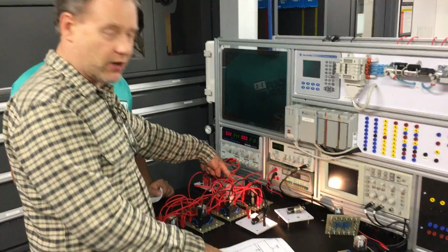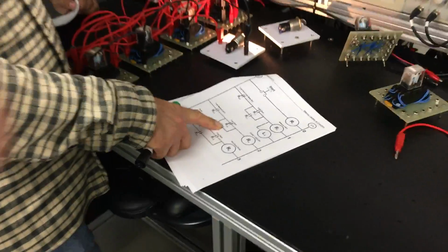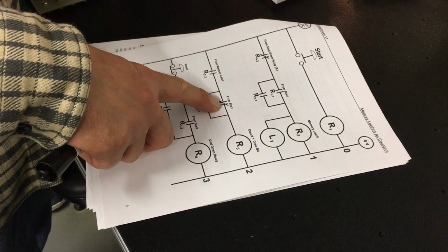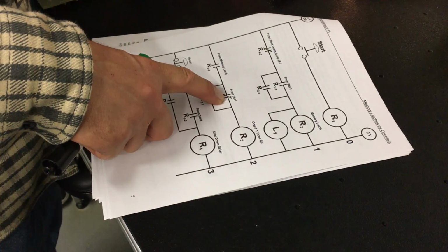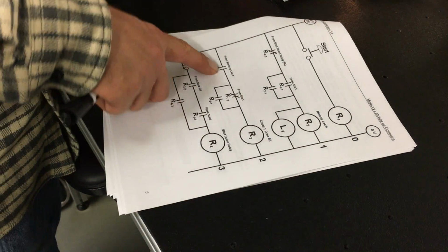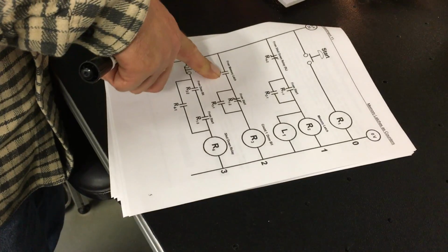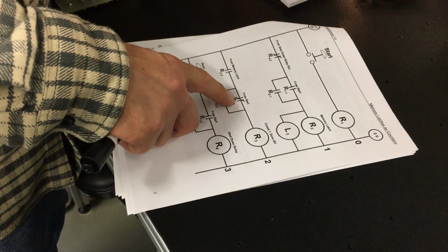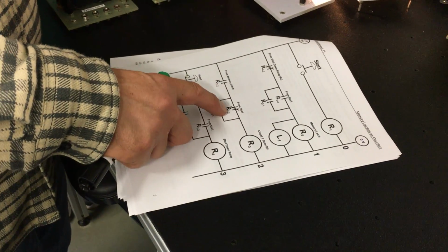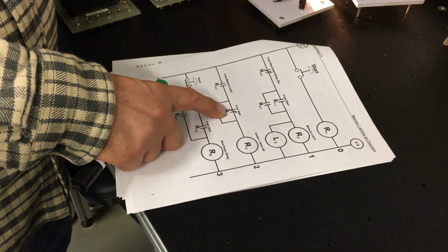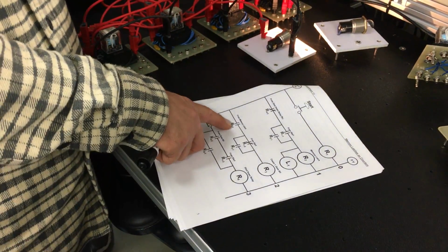So the second rung is this. As long as my finger's on the button, that's open, right? Now, it just so happens that when my finger's on the button, that latches onto the fact that the event has happened, so that is now closed. Now, when I release it, this tells me that it's no longer happening, or specifically, all this really tells me is that the event is not happening. This is telling me that it did happen. So the logic here is that it did happen and it's not happening anymore.